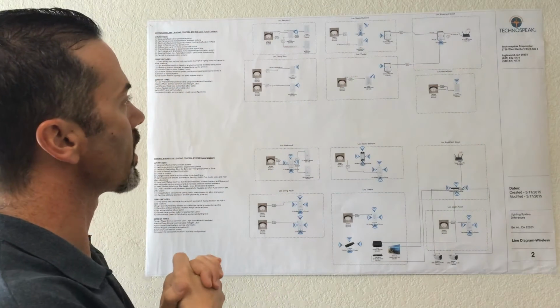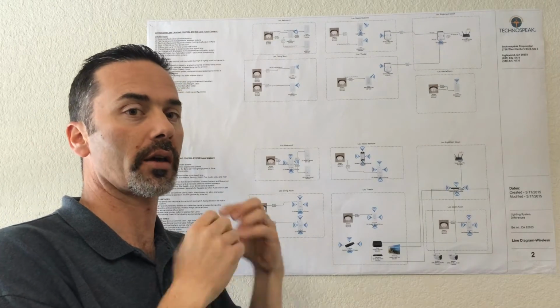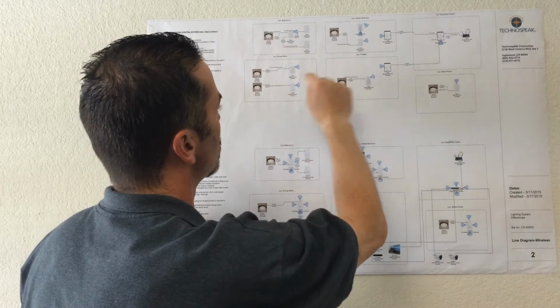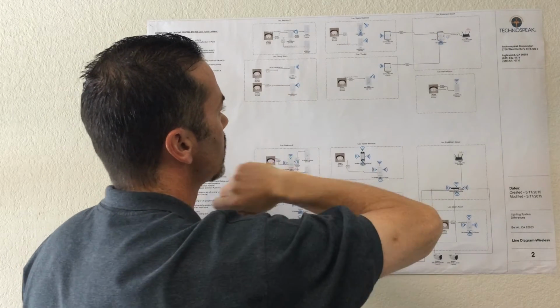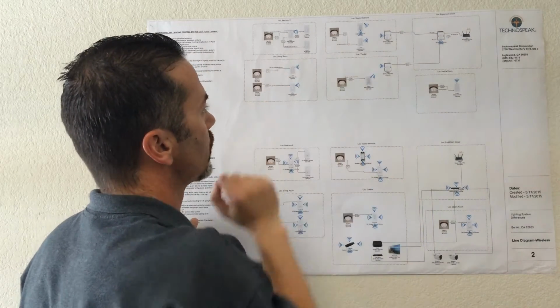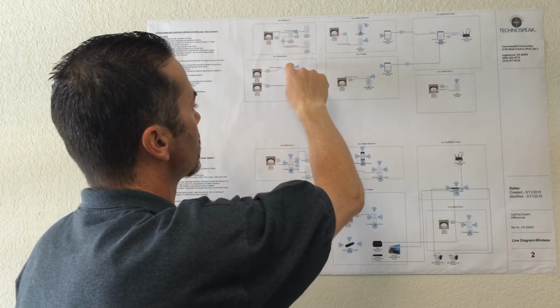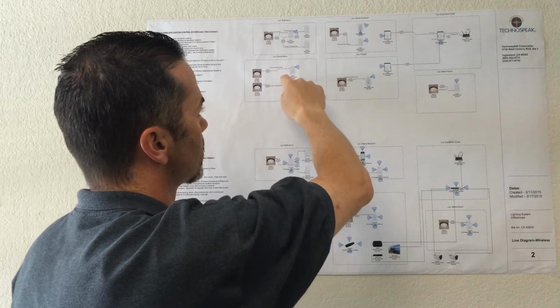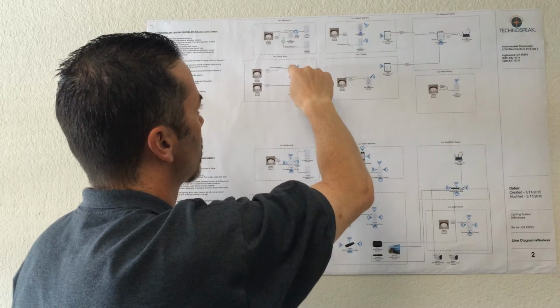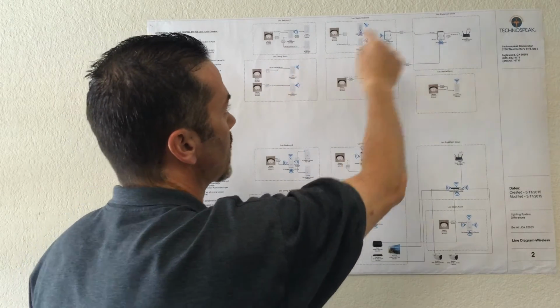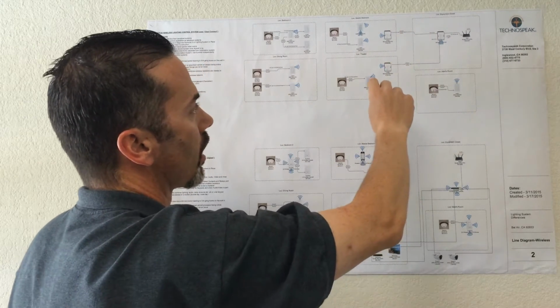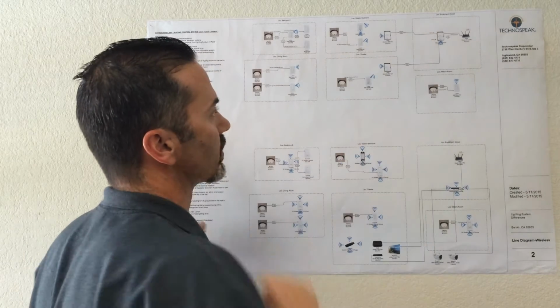This is an RF star-based communication topology, which means that each individual light switch is communicating with an aux repeater or communicating with the main repeater. They are not communicating with each other. So basically one of these is going to send a signal to this main repeater. This main repeater is going to send a signal back, or this is an aux repeater rather. So in this particular case, this one would go to the main repeater, and so on and so forth, or whatever the closest repeater was. These all act as one brain.